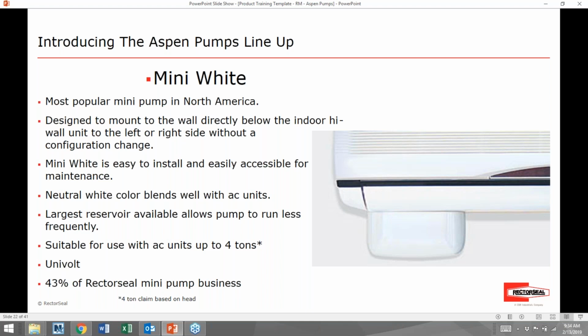It has the largest reservoir available of all pumps, which means it will run much less frequently, which is a little bit important because any surface mount pump is going to tend to be louder because it's in the occupied space. So if we can run less frequently, then we have an advantage. The Mini White is suitable for AC units up to 4 tons. The 4-ton claim on this sheet and all the rest that we're going to talk about today is, of course, based on head. Head is the vertical distance the pump will be pumping. So the higher the head goes, the lower the performance of the pump in terms of tons.